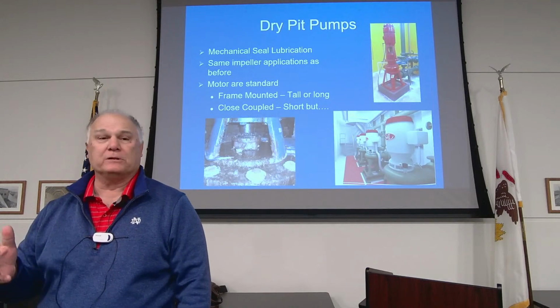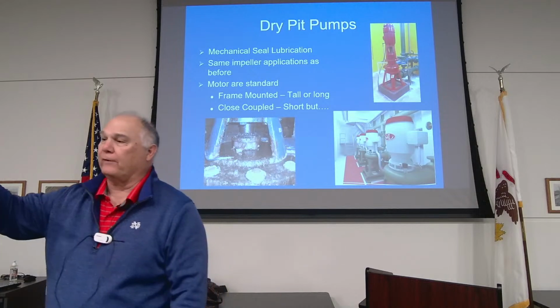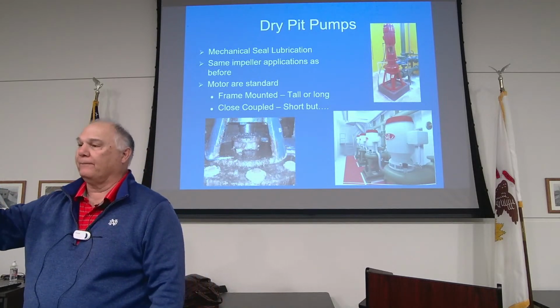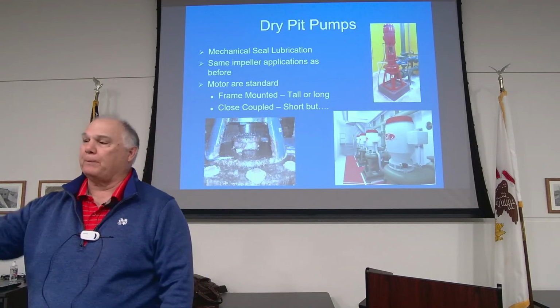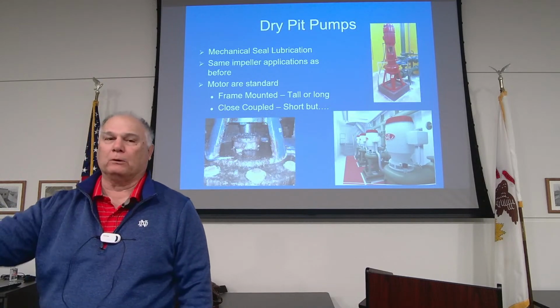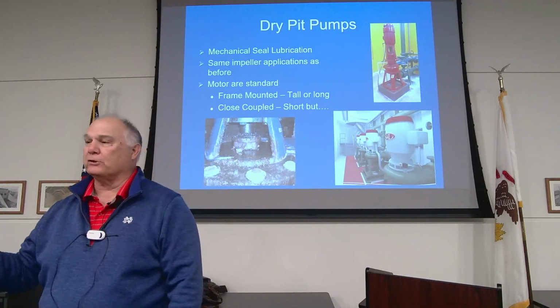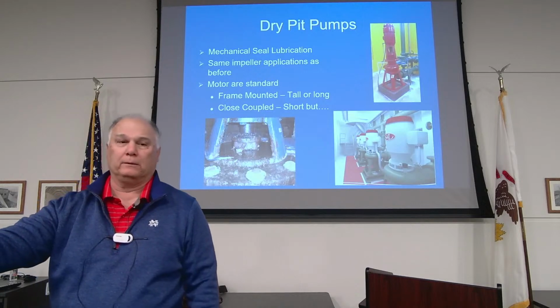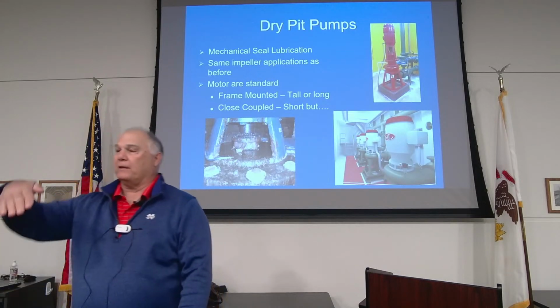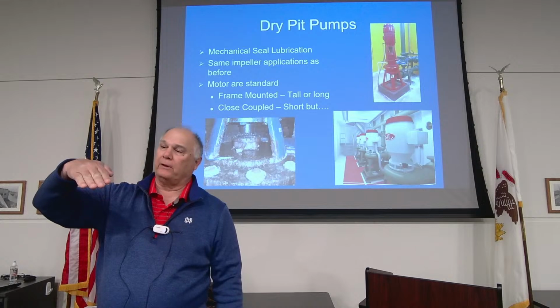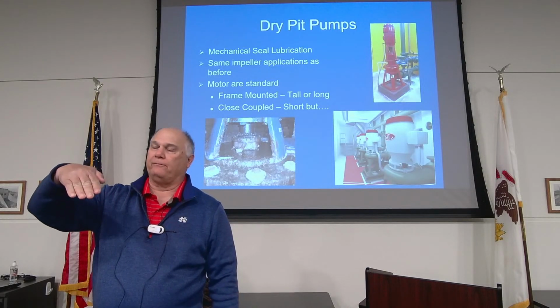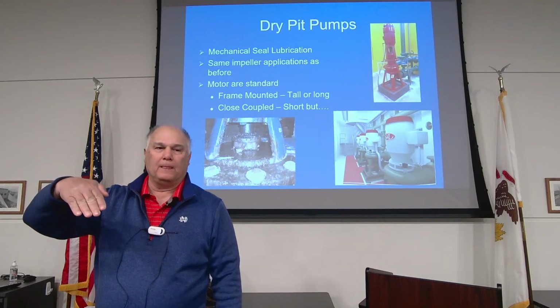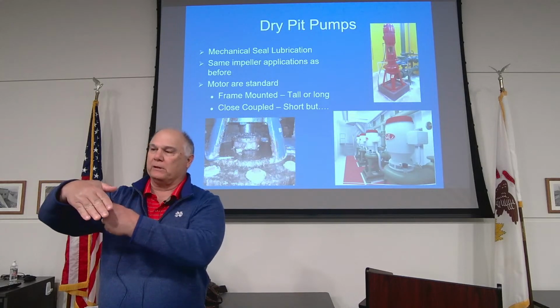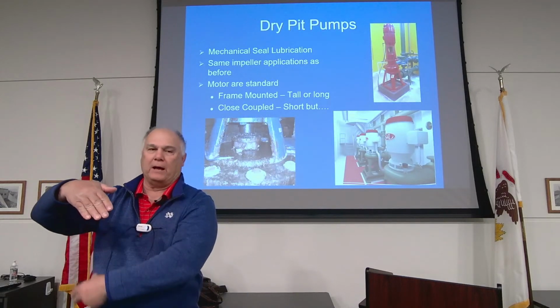Because your check valve is going to be a restriction, right? If you're trying to pump this rag or this flushable wipe, you've got to get that flushable wipe into the force main. But if that check valve, at 100 gallons a minute, is only going to open up 15% of the way, all that debris is going to get stuck behind that check valve, down through the pump.